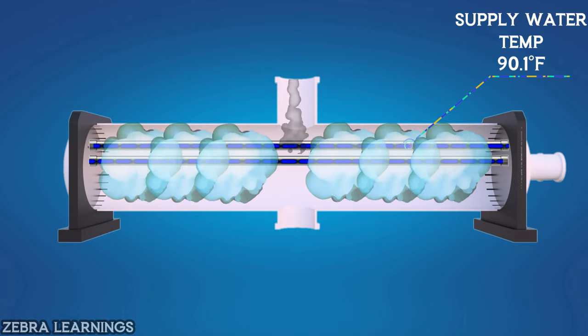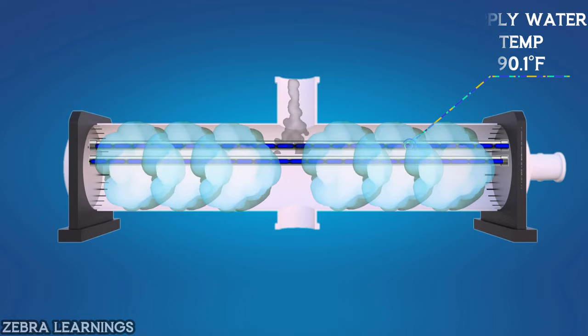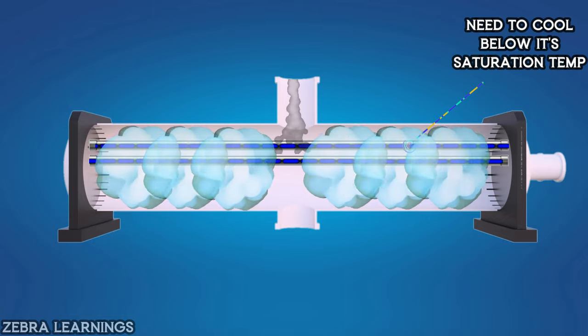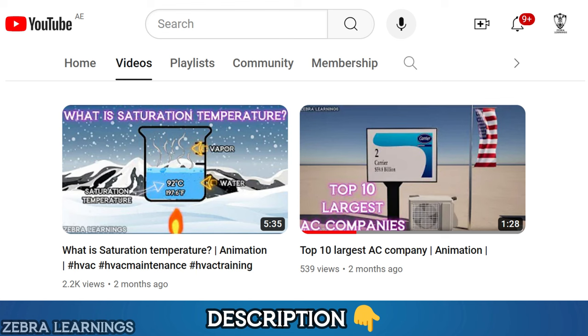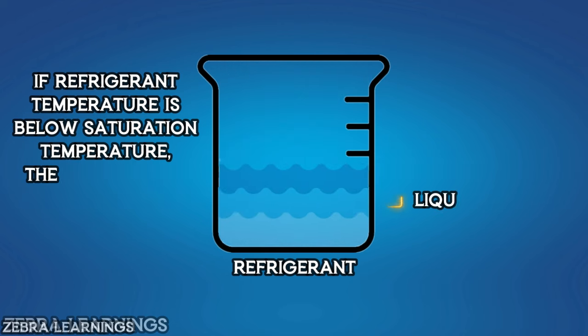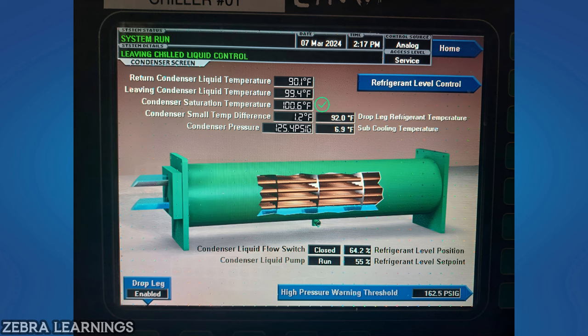If the refrigerant remains in vapor state, it will increase the pressure in the condenser, which can lead to chiller surge. To convert the refrigerant from vapor to liquid, we need to cool it below its saturation temperature. If the refrigerant is above its saturation temperature it will be in a vapor state; if below, it will be in a liquid state. The saturation temperature of the refrigerant can be known through the display of the chiller.